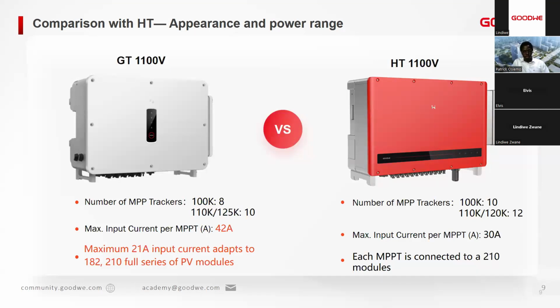Looking at the MPPT trackers, on the GT, the 100 has 8 MPPT trackers, yet the HT on the 100 had 10. On the 110 and 125, we have 10 MPPT trackers, and on the HT 110 and 120 it is 12 MPPT trackers. The reduction is mostly because we have increased the current. As you can see, the max input current per MPPT is 42 amperes compared to the 30 amperes the HT offered. Meaning on the GT, we can support the 182 and 210 full series of PV modules, whereas the HT could support only the 210 PV modules.